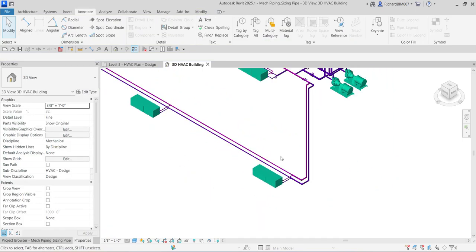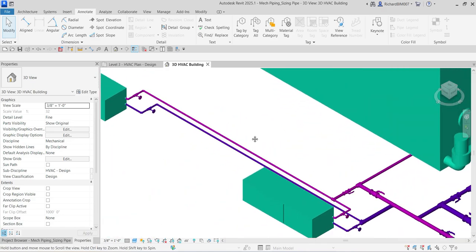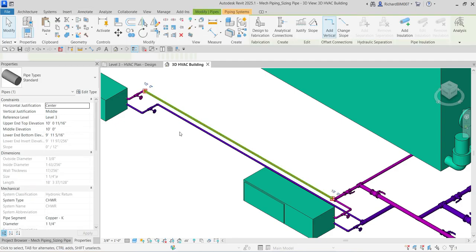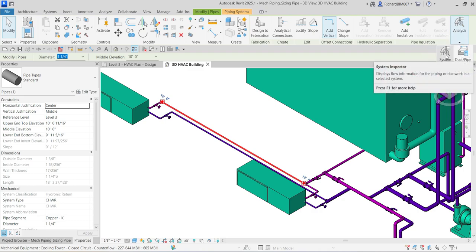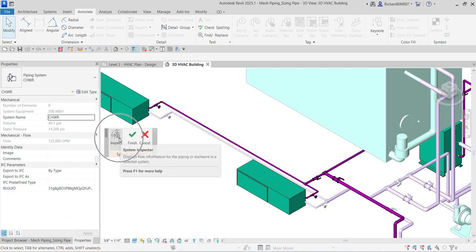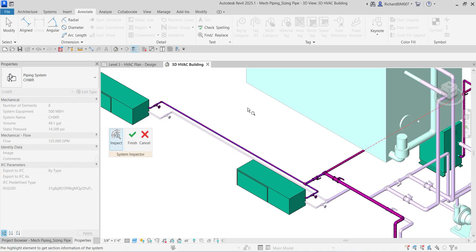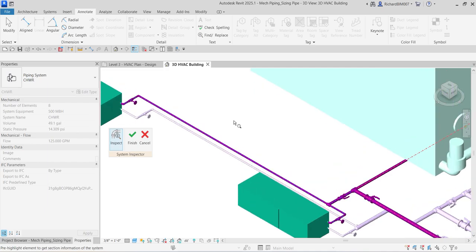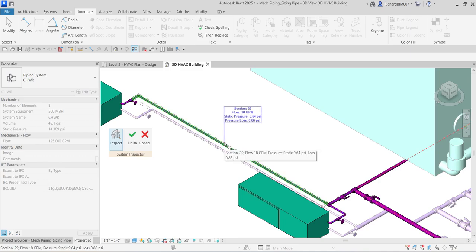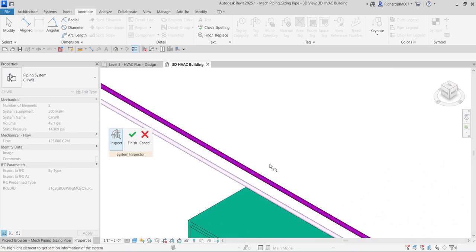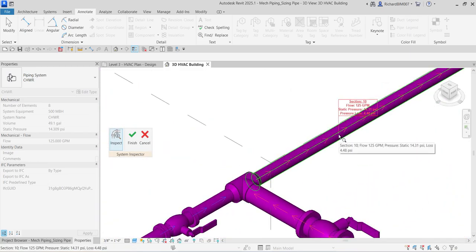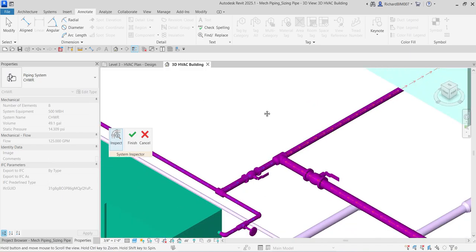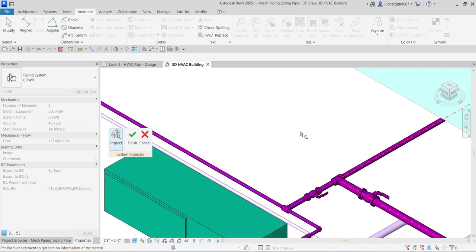To start the System Inspector, select the return pipe between the water source heat pumps. Go to Analysis and click 'System Inspector,' then select 'Inspect.' Placing the cursor over a pipe section reveals the flow, static pressure, and pressure loss for that segment. Zoom in and you'll also see arrows on the pipes indicating flow direction for both the main line and branches.